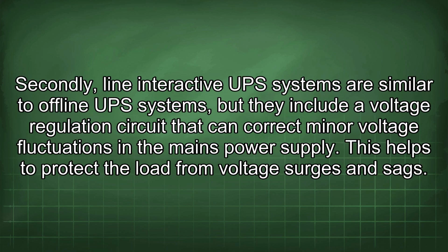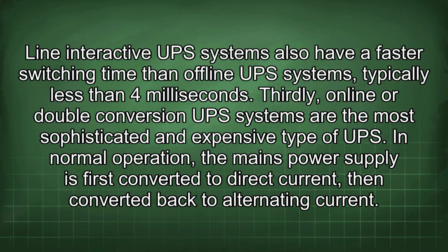Secondly, line interactive UPS systems are similar to offline UPS systems, but they include a voltage regulation circuit that can correct minor voltage fluctuations in the mains power supply. This helps to protect the load from voltage surges and sags. Line interactive UPS systems also have a faster switching time than offline UPS systems, typically less than 4 milliseconds.